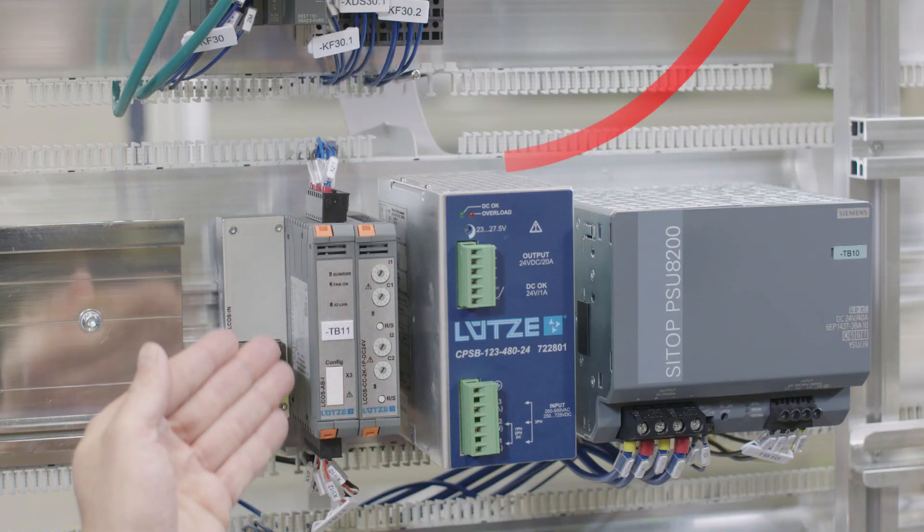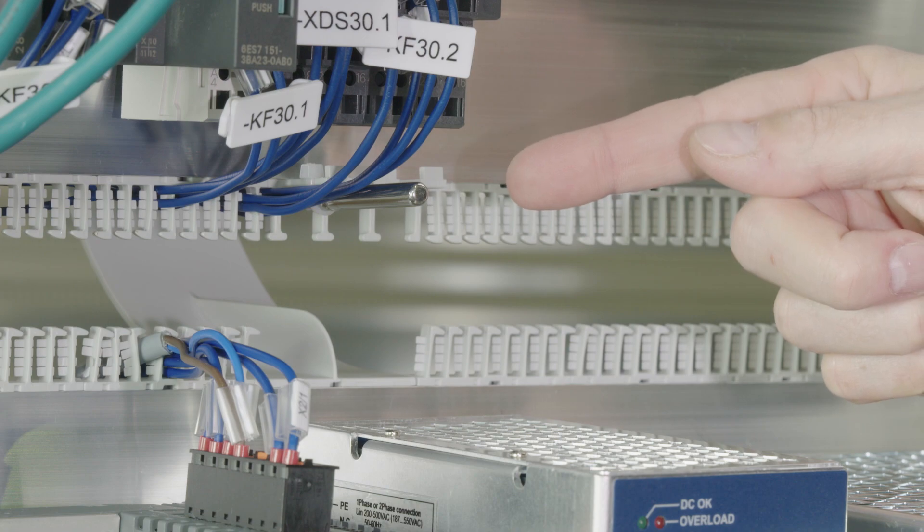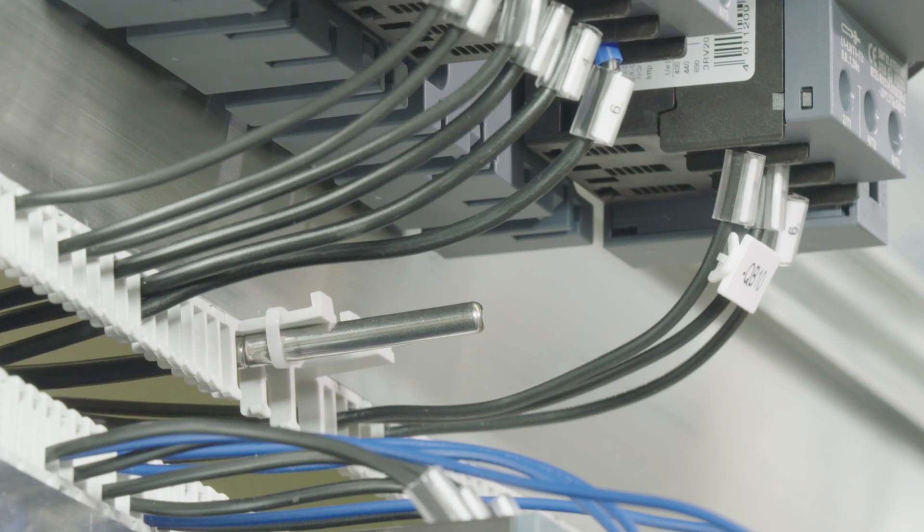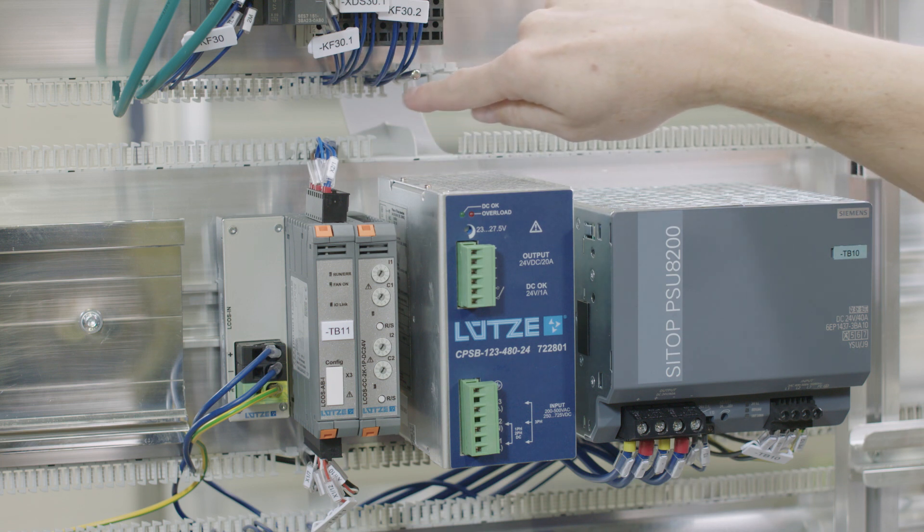The control unit also includes three PT100 sensors, which switch the air blower on or off when the interior of the cabinet is above the required temperature. The temperature sensors are placed underneath sensitive components where hotspots could arise.